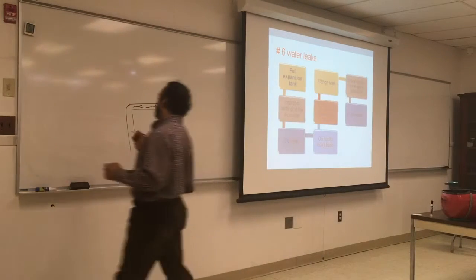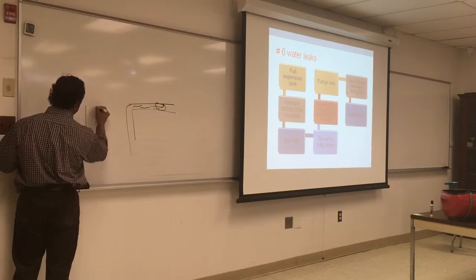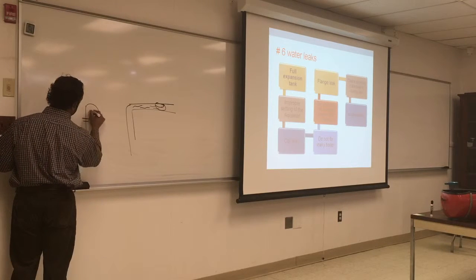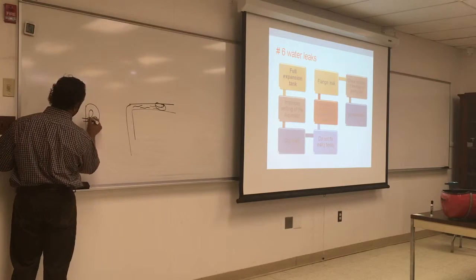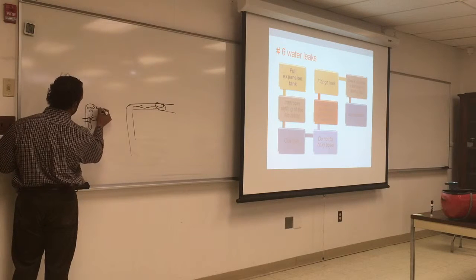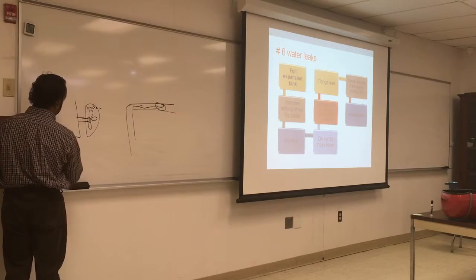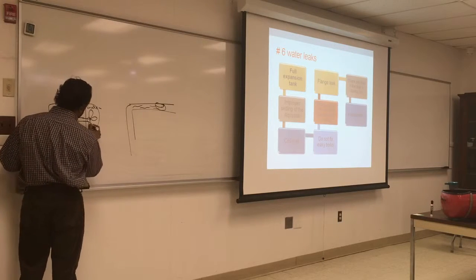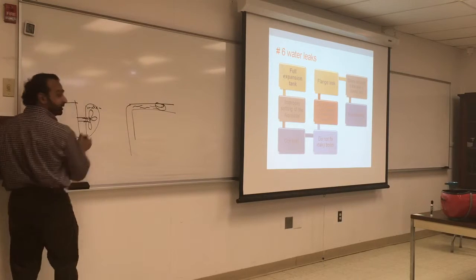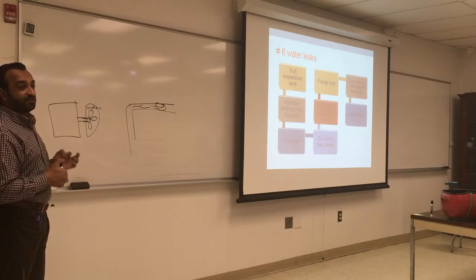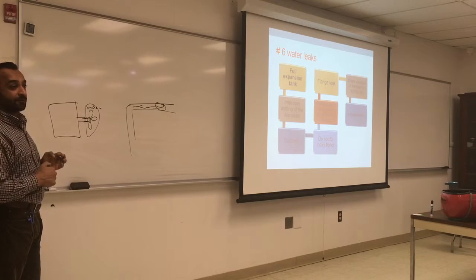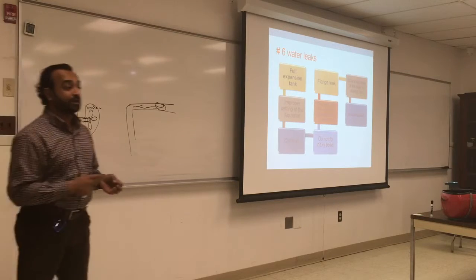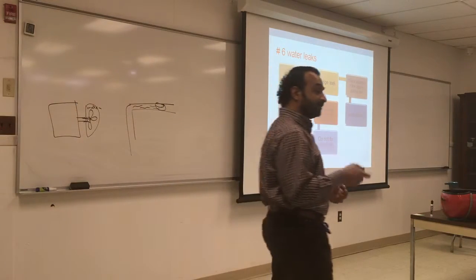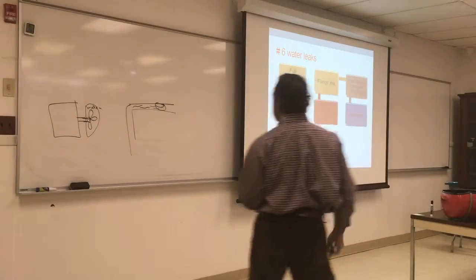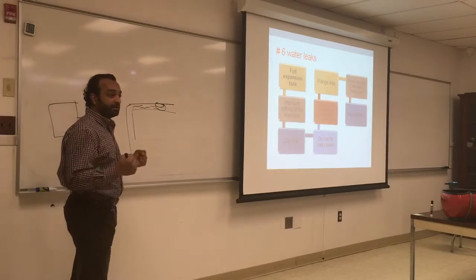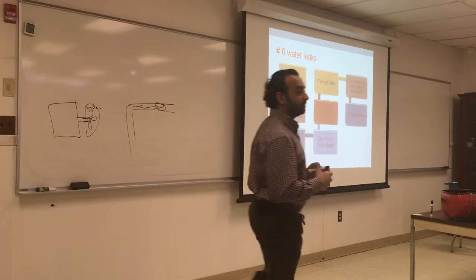into the motor. So if you look at the pump on the inside, this is the shaft, this is the impeller. There's water in here. This is the motor. So how come the water is not coming out from this little opening? It's very, very small and sized correctly, like to the micron, so it will not move. Over time, with spinning, it might leak. And usually they put a lot of flanges and bushings in here. They'll provide some kind of cushion for the water not to leak.